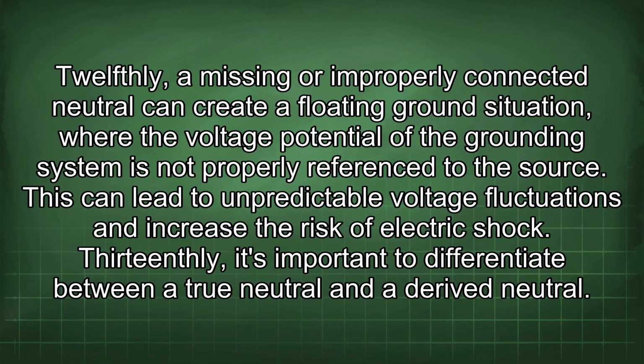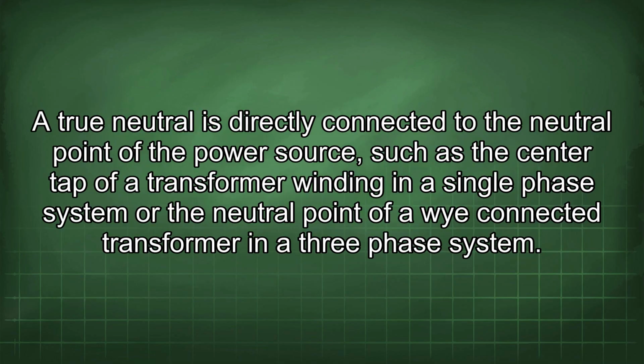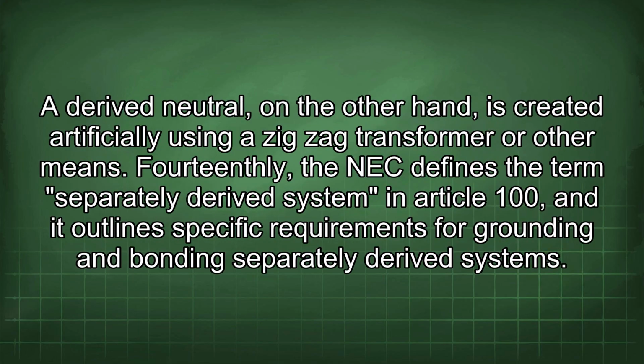13thly, it's important to differentiate between a true neutral and a derived neutral. A true neutral is directly connected to the neutral point of the power source, such as the center tap of a transformer winding in a single-phase system or the neutral point of a Y-connected transformer in a three-phase system. A derived neutral, on the other hand, is created artificially using a zigzag transformer or other means.